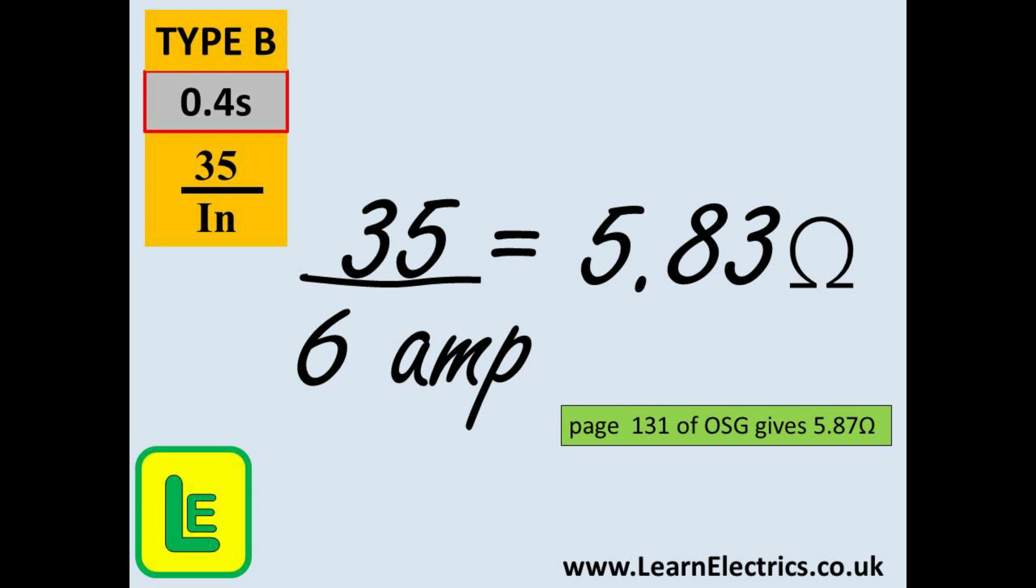In this example we will use a 6 amp type B circuit breaker. 35 divided by 6 will give us 5.83 ohms. You will need a calculator for this and do not be afraid to write down your calculations. If you get a wrong number you can quickly trace your mistake. Look at the table B6 in the blue on-site guide. In my book it is on page 131. The on-site guide gives a maximum ZS value of 5.87 ohms. And I think you will agree that we are pretty much there with the value that we have just calculated. Nobody is going to fuss over 4 one hundredths of an ohm.